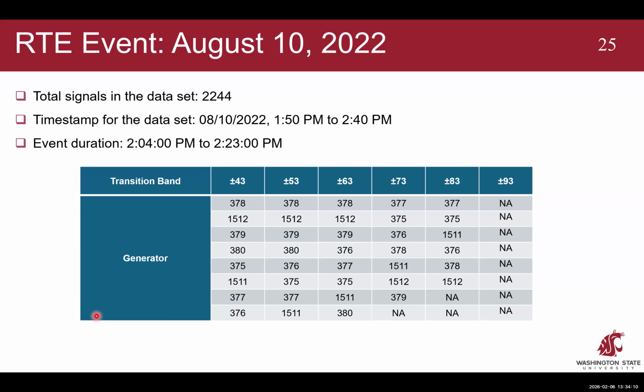Because we don't know how much band or amplitude to expect in a real event, we start from some low value. Here we've shown that when the band is 43, all of these signals pass the test, meaning there's a significant oscillation with amplitude more than 43 megawatts.